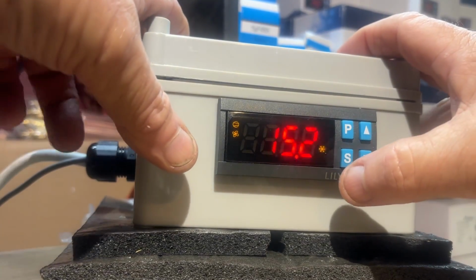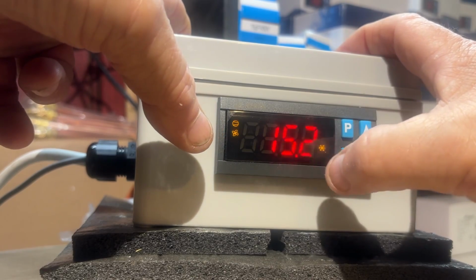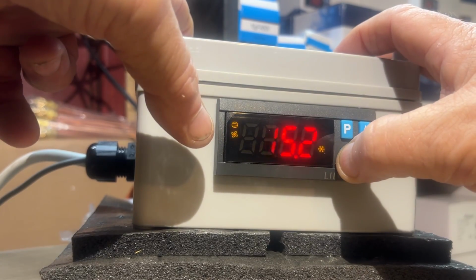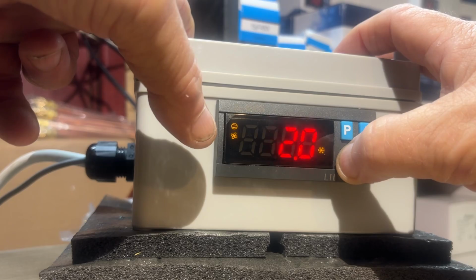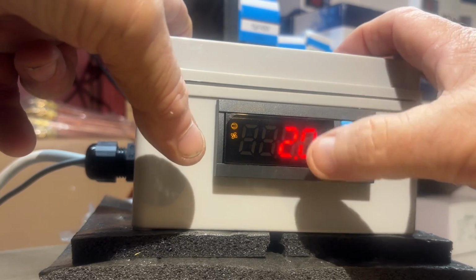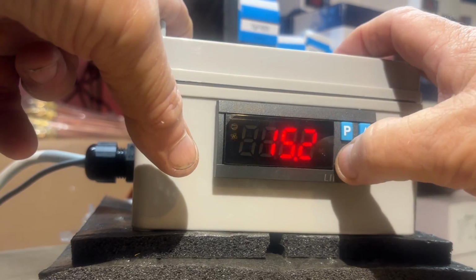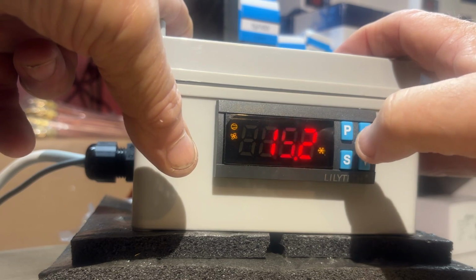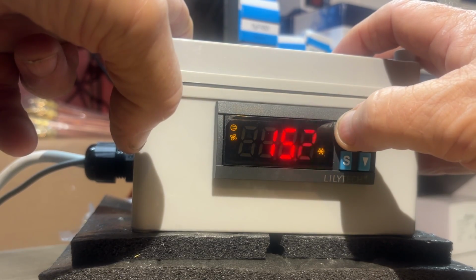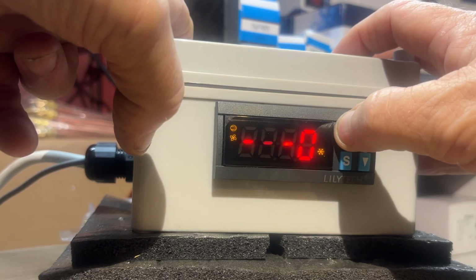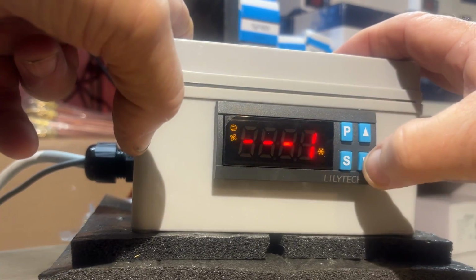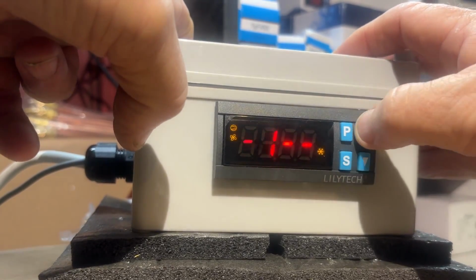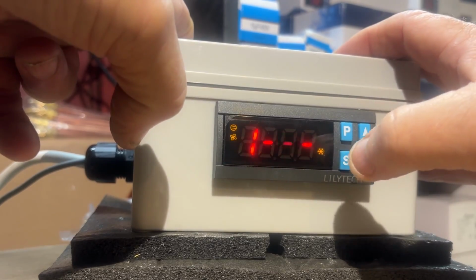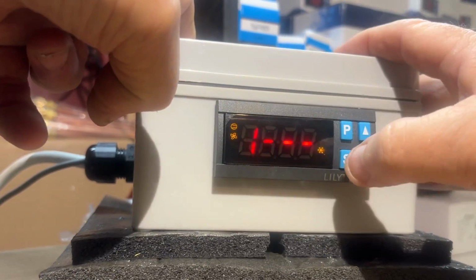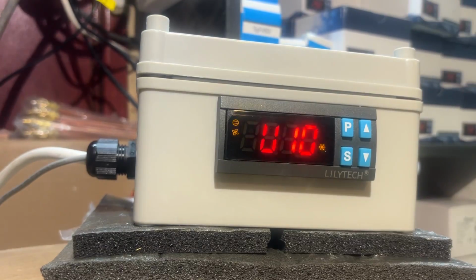So this comes set at -15, but I've already set it to 2. So it's set at 2. So 2 is the cutout. Press it again, it goes off. To get into the parameters, you've got to press up, down, up, down, up, down, up. Once one is right over here, press set. Now you're into the parameters.